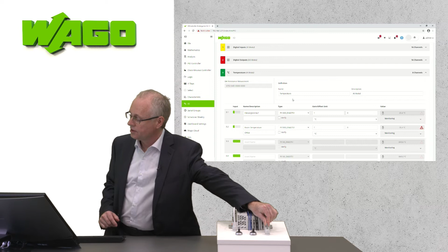Now we need an output signal for our heating valve. Therefore, we use the digital output module, and we will look again for the next free channel, and we will assign the data point name, heating valve. Again, the additional description. We can select a range from 0 to 100%, and you can also select in which way the valve is controlled by the output. In this case, we select the PWM signal.